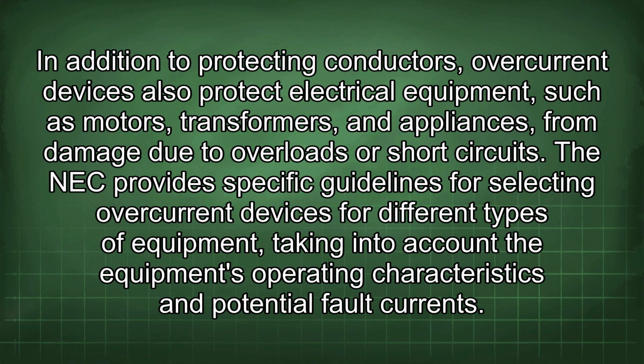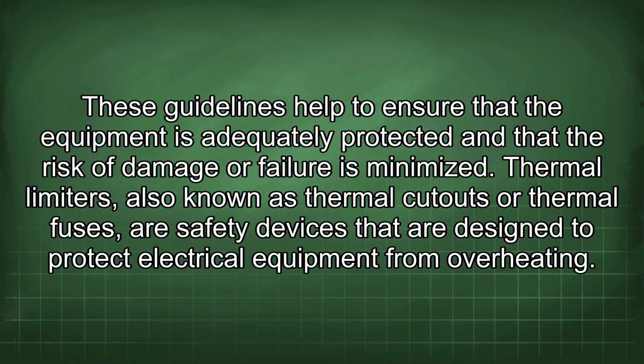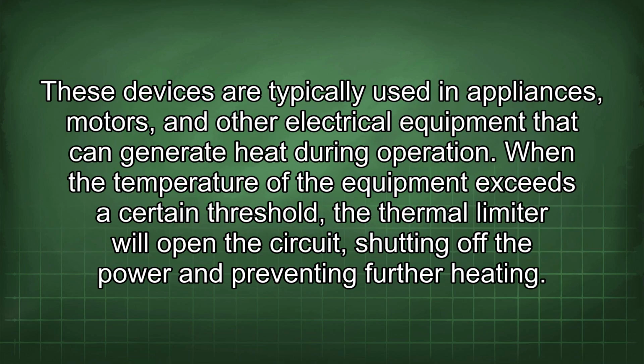The NEC provides specific guidelines for selecting overcurrent devices for different types of equipment, taking into account the equipment's operating characteristics and potential fault currents. These guidelines help to ensure that the equipment is adequately protected and that the risk of damage or failure is minimized. Thermal limiters, also known as thermal cutouts or thermal fuses, are safety devices that are designed to protect electrical equipment from overheating. These devices are typically used in appliances, motors, and other electrical equipment that can generate heat during operation. When the temperature of the equipment exceeds a certain threshold, the thermal limiter will open the circuit, shutting off the power and preventing further heating.